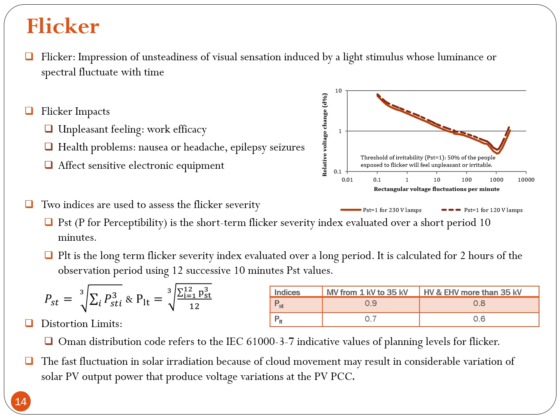Oman distribution codes refer to IEC 61000-3-7 indicative values for the planning levels of flicker, having a 0.9 limit for PST and a 0.7 limit for PLT. The fast fluctuation in the solar radiation because of cloud movements may result in considerable variation of the solar PV output power that produces voltage variation at the PV point of common coupling.